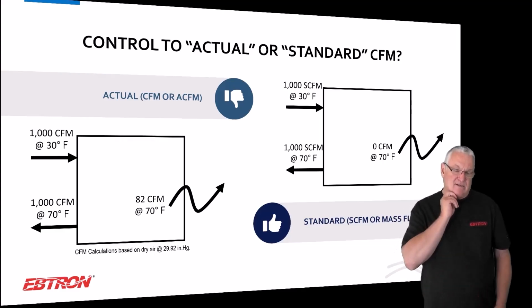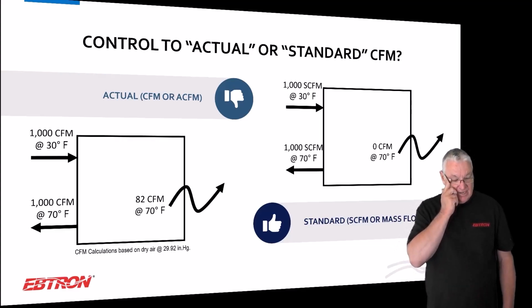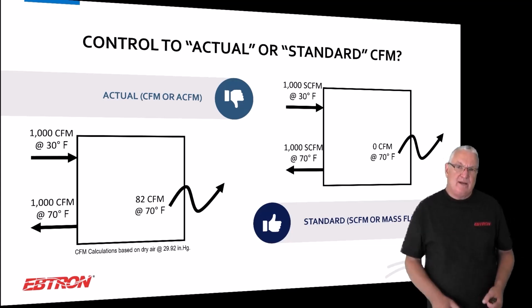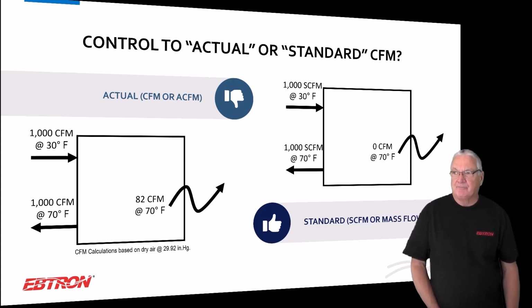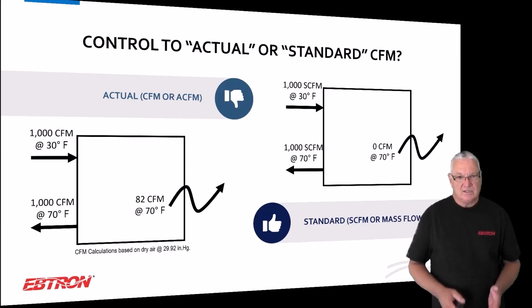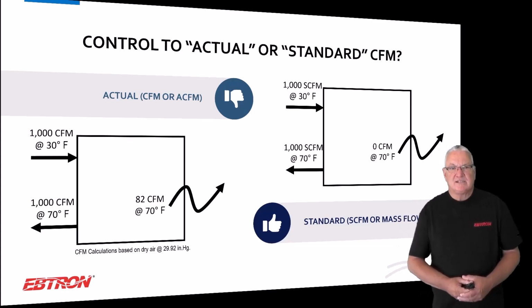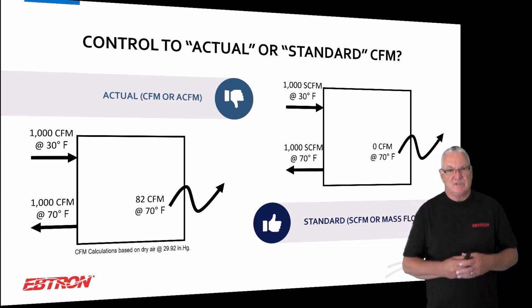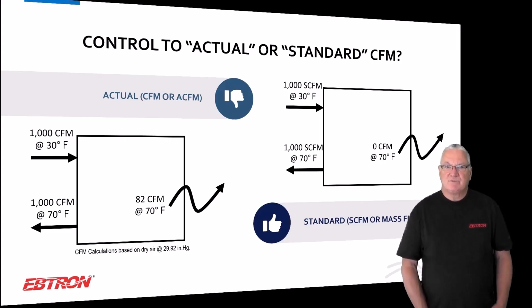The reason that this matters on the healthcare side is you can get away with this after you set your systems up, if the supply air temperatures aren't changing and the return air temperatures aren't changing. But if you have anything that's changing there, you're adding a little more uncertainty to your pressurization. And you really should be thinking about standard CFM, which on the EBTRON is very simple. You just set it to output standard CFM. It's just something I like to put in for those of you that are really doing real precise control, particularly as spaces get tighter and tighter and tighter, okay?